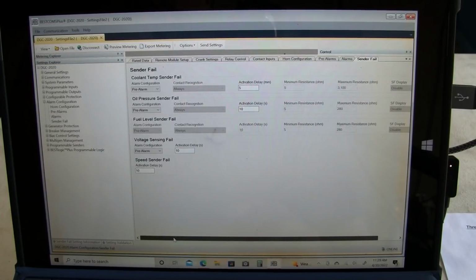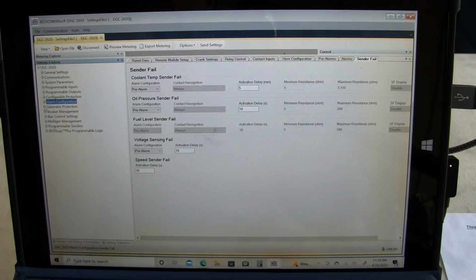Let's see. So, if our coolant temp sensor fails or oil pressure sensor fails, it will go into pre-alarm. Yeah, I did set that. It will not shut the genset down, but it will let you know that it's no longer able to detect oil pressure or water temp. Generator protection.